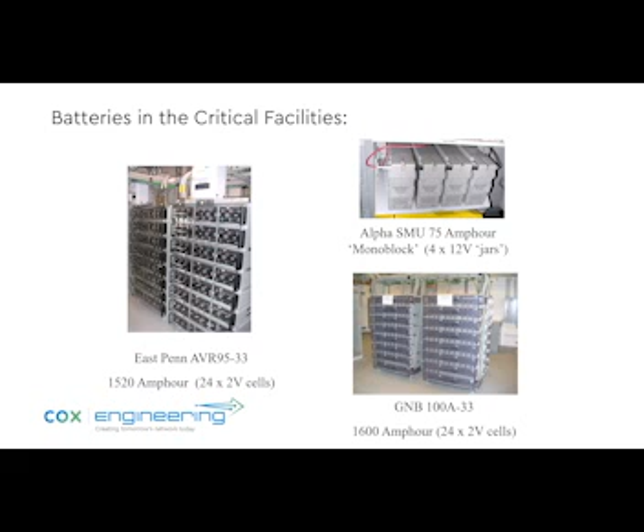So a sizing example: let's say you have a 2000 amp plant, you need 4 hours of battery reserve, and the existing load is about 1400 amps. You have to consider what's the max capacity that this DC plant can expand to, because then you're going to need that much battery space. The thing about batteries, of course, is you only buy as many as you need, and they have maybe a 10 to 15 year life depending on the type of battery.